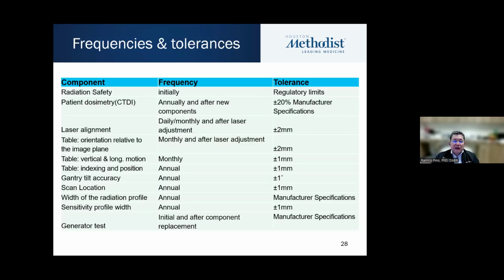Radiation safety is typically done initially unless you have a significant change in the shielding of the room or a massive change in the X-ray tube. CTDI should be measured annually and after any new component. The laser alignment is recommended to be done daily, monthly, and after any laser adjustments. And I'm listing the tolerances here at the right.